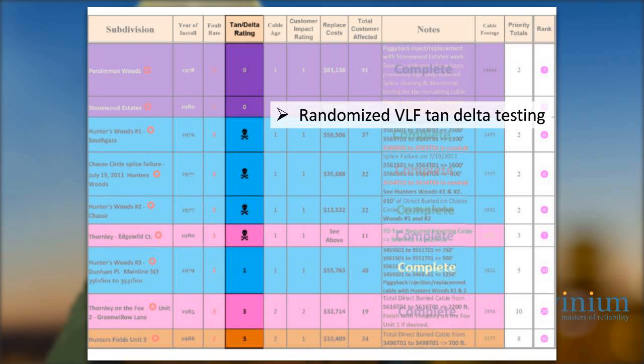One of the clever things people pick up on when they see Steve's spreadsheet is the skull and crossbones. Those indicate places where Steve had the test rig, and before we got to the rated voltage of the cable, the sine wave at the top of the amplitude starts to collapse. That's an indication the cable is on its way to failure, and at that point we immediately shut down the machine. The spans that failed VLF, meaning they're a ticking time bomb and imminent failure, we didn't change our plan for injection — those spans were still injected and went on their way.